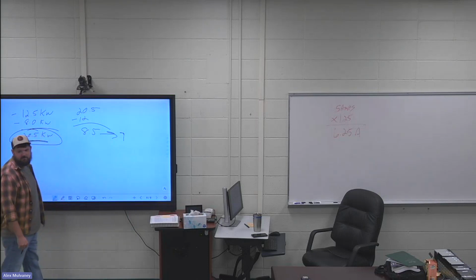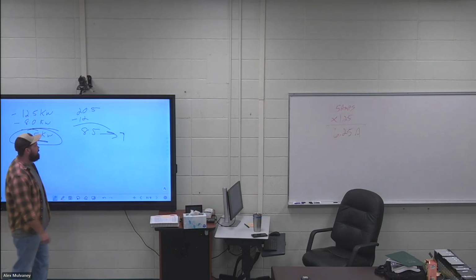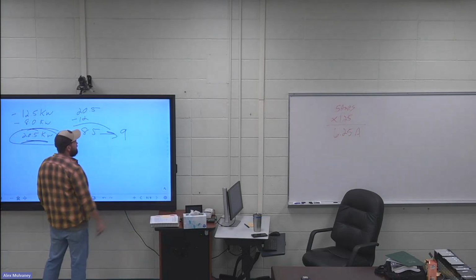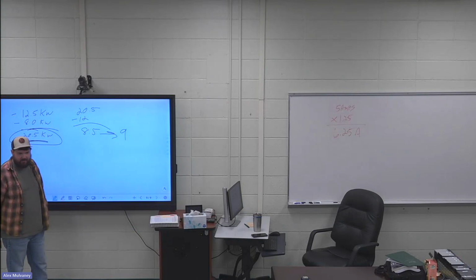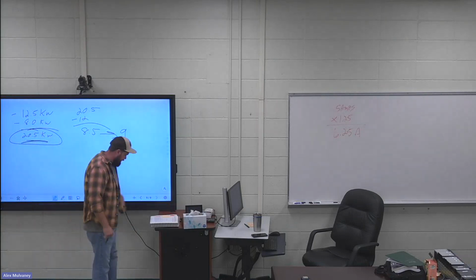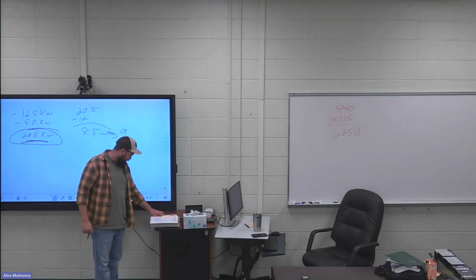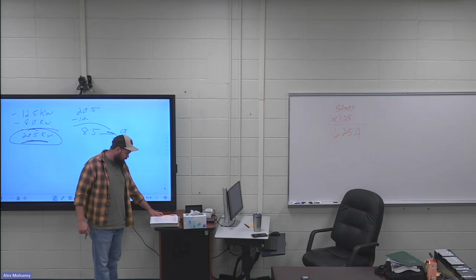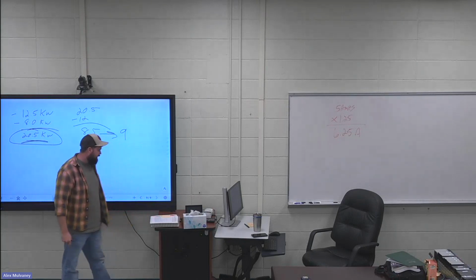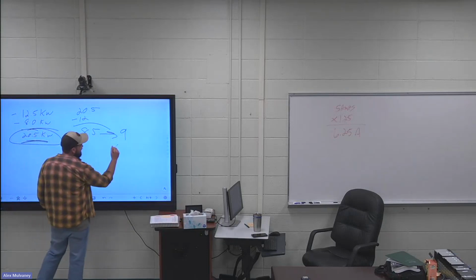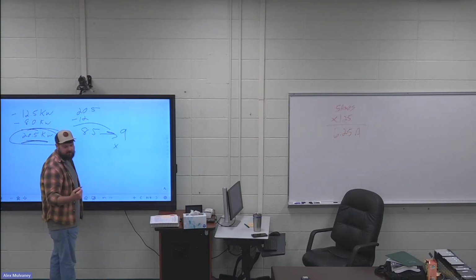To me that's stupid confusing. That doesn't look like a 9. But it rounds to 9, and that's what we have to use, right? So it says that because 0.5 is a major fraction, the result is rounded to 9 kilowatts. Multiply this by 5%. So 9 times 5, what's 5% written as a decimal?